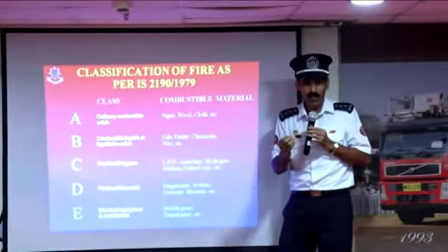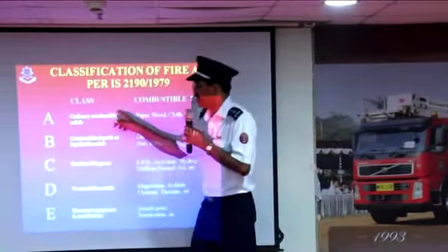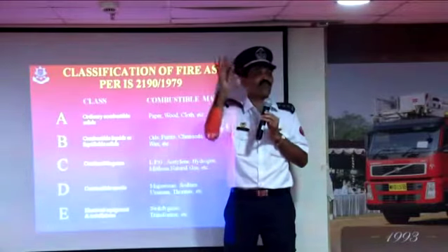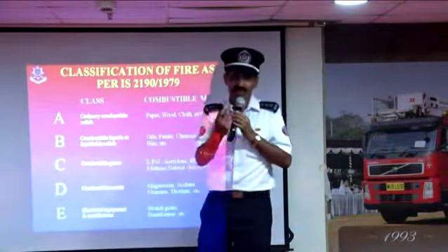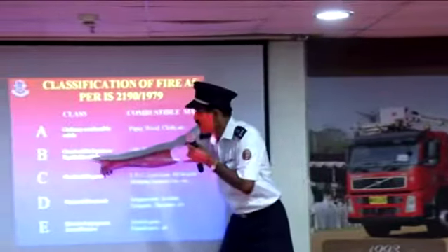Now stop for a while discussing these 4 or 5 types of fire, because there are some exceptions in this. In A, I say ordinary combustible solid, not each and every solid. The first exception is the burning solid substances which on heating get melted. That is the exception for this class A, because it goes to the liquid stage. So that will be in B.